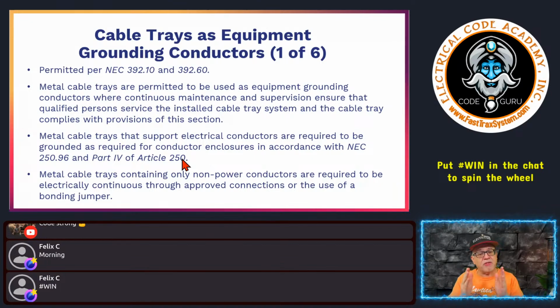If you have any parts that are not continuous, and a cable tray, again, like a ladder style or whatnot, it's just basically a U-shaped channel that supports conductors and cables. Okay, and it's not a raceway, so you don't treat it as a raceway. Although the code will talk about things when it comes to, we saw 392.22, how many conductors or cables you can put in it, and then how that affects the ampacity in 392.80 by how many conductors or cables you put in it. But it's still not a raceway. It's still just a supporting system, okay?